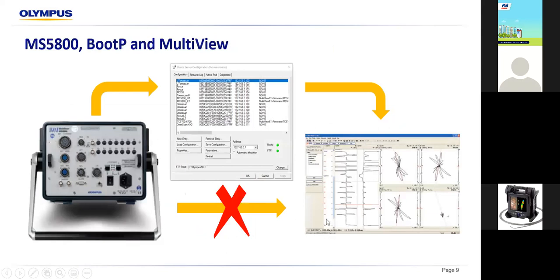So this is the setup that we will be using. You have your equipment here, which is the MS5800. Before opening your MultiView, you need a communicator, a software that communicates between the MS5800 and the MultiView, which is the BootP. Aside from installing your MultiView, you also need to install your BootP so that there is better communication between the hardware and the software. And lastly, the software you're going to use while doing your tube inspection will be the MultiView.